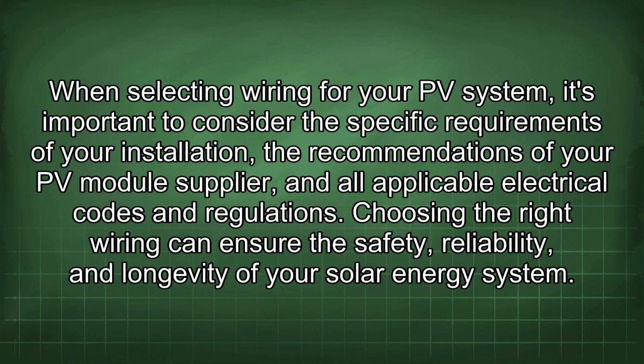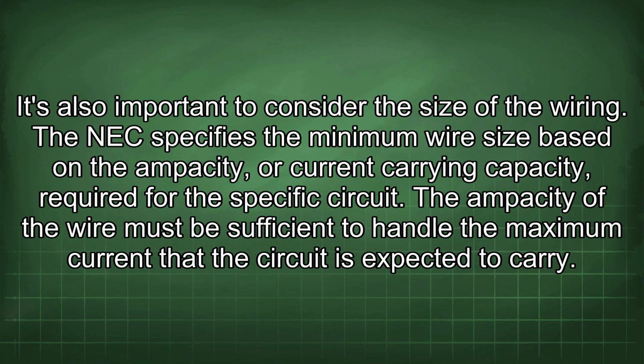When selecting wiring for your PV system, it's important to consider the specific requirements of your installation, the recommendations of your PV module supplier, and all applicable electrical codes and regulations. Choosing the right wiring can ensure the safety, reliability, and longevity of your solar energy system. It's also important to consider the size of the wiring. The NEC specifies the minimum wire size based on the ampacity, or current carrying capacity, required for the specific circuit. The ampacity of the wire must be sufficient to handle the maximum current that the circuit is expected to carry.